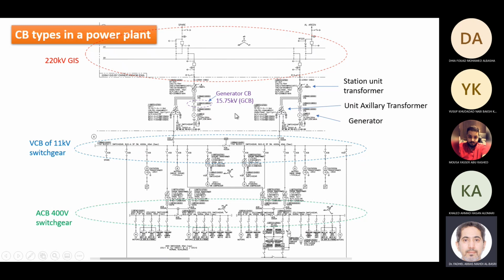In the breaker here for a generator, there is one breaker which is not clearly shown. So this is a generator circuit breaker shown here. We also have other breakers. This transformer steps down to 11 kV, so we have a breaker shown as VCB. I don't know if you can see this. This is a VCB, vacuum circuit breaker. But at the voltage here, at 220 kV, I have GIS, or gas insulated switchgear.